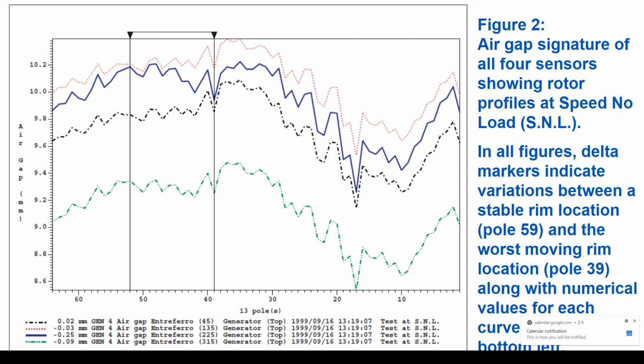And what I decided to do was take tests on all 5 units, and what we did is we ran the unit from speed no load up to 42 megawatts, and we looked at the results. So we did unit number 1, it was fine. We looked at number 2, which had failed, it was fine. So they had mixed feelings because they were happy that they didn't find anything wrong, but at the same time we didn't find any evidence that would tell us what happened. So we moved on to unit number 3, it was fine.